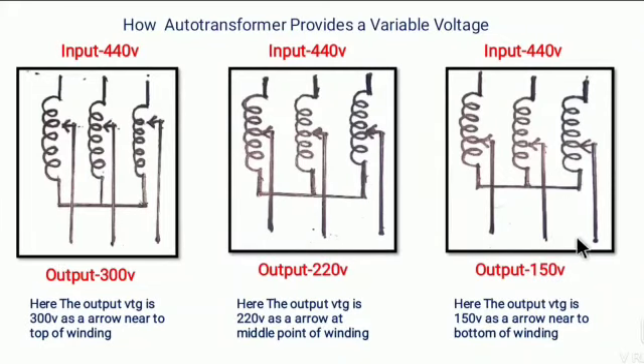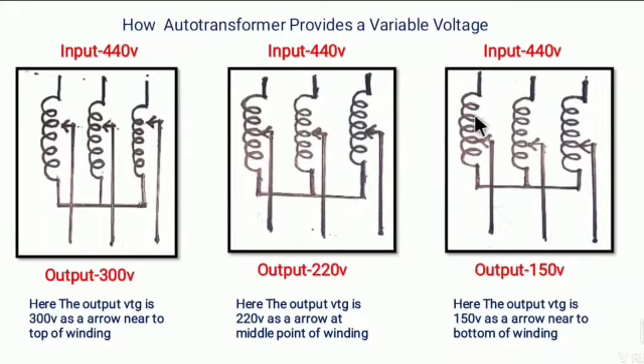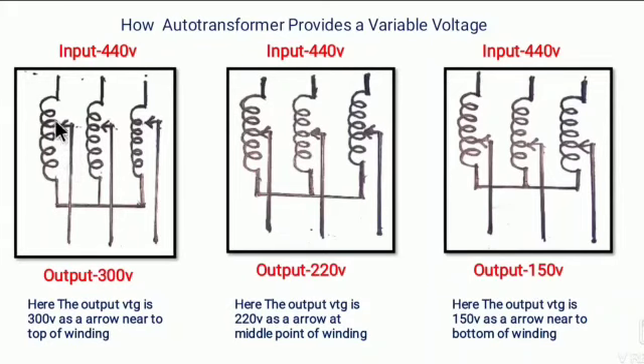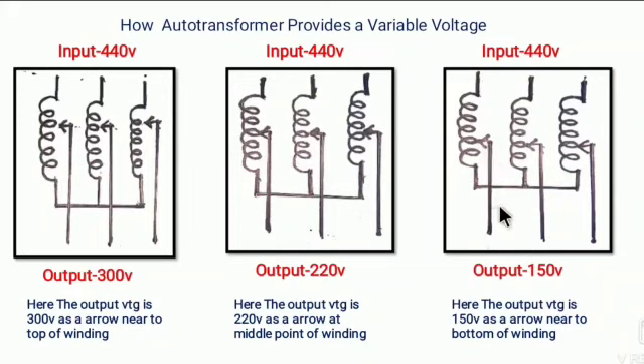From these three diagrams we conclude that the input voltage is 440V in all cases, while the output voltage is 300V in the first, 220V in the second, and 150V in the third. The output voltage decreases as the movable contact moves toward the lower points, because the number of turns consumed by the contact reduces — as the number of turns decreases, the output voltage also decreases. Thank you.